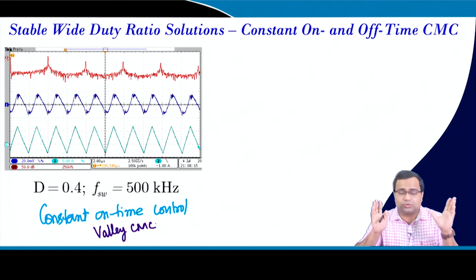Now, coming back to our original problem, that means low duty ratio operation. If you want to achieve low duty ratio operation in a converter, you simply use a constant on time control. So, this is the on time. Since this on time is fixed by a timer, you do not need any comparator condition. That means there is no comparator action in this duration. So, it is feasible even for a very small on time. So, for high frequency applications, this can be used.